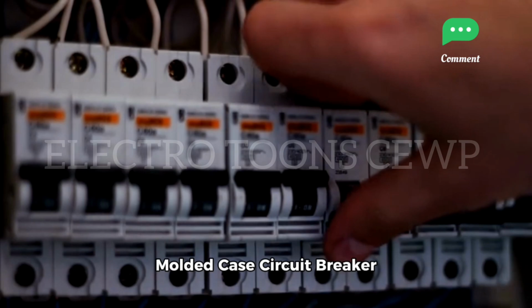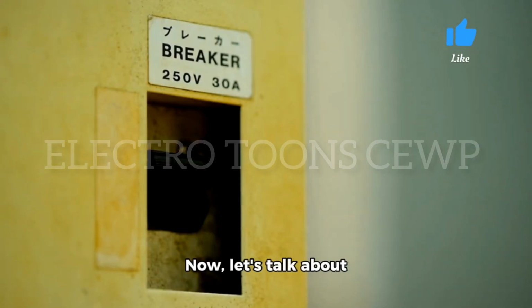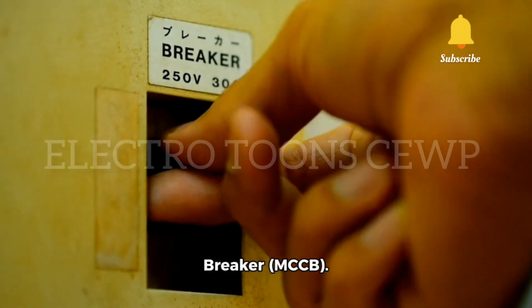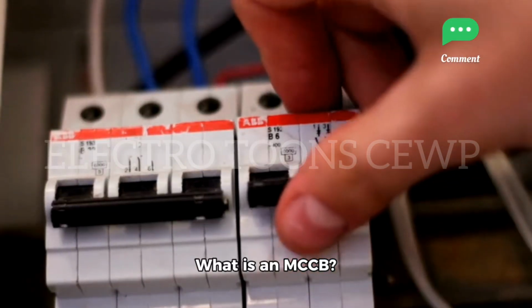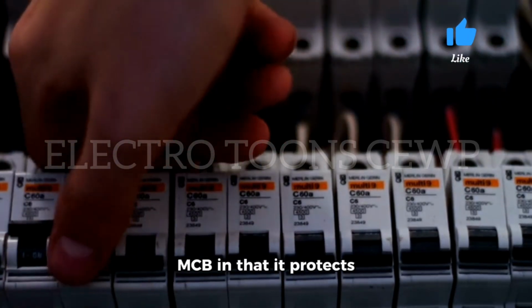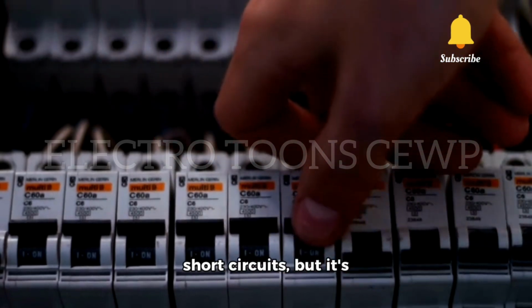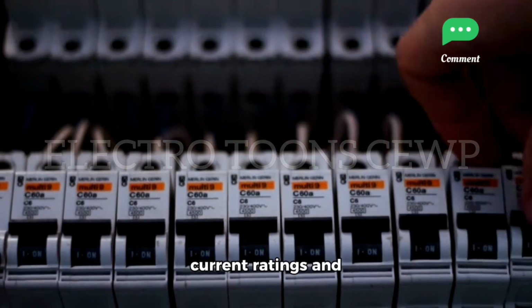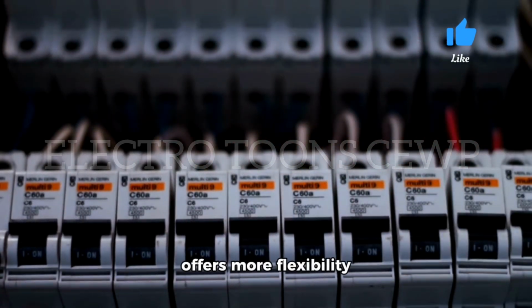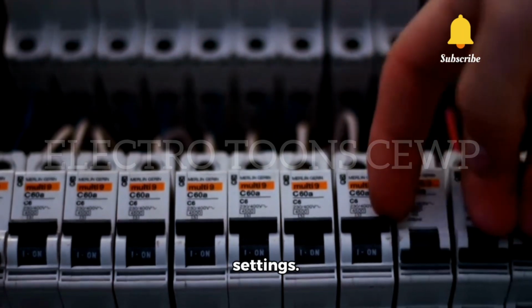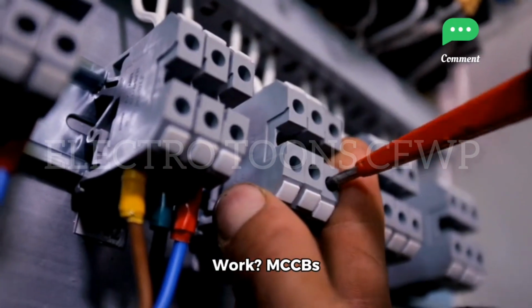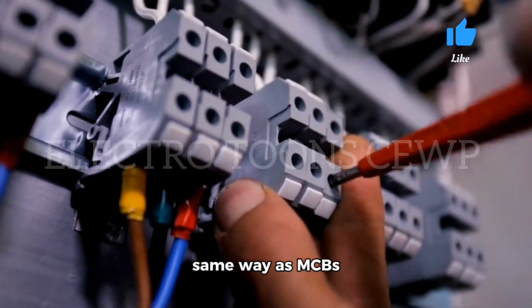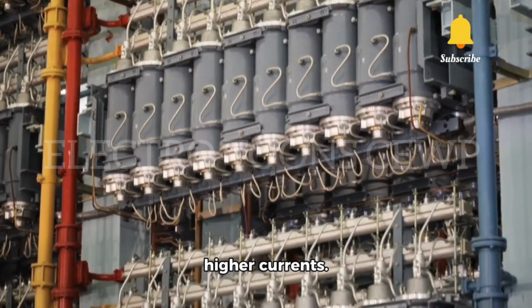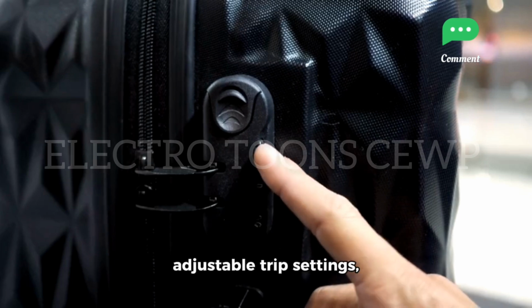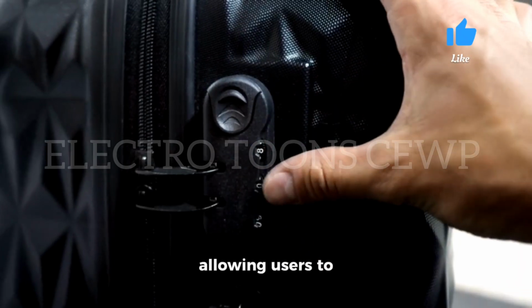MCCB, molded case circuit breaker. Now, let's talk about the molded case circuit breaker, MCCB. What is an MCCB? An MCCB is similar to an MCB in that it protects against overloads and short circuits, but it's designed for higher current ratings and offers more flexibility in terms of protection settings. How does an MCCB work? MCCBs operate in the same way as MCBs but can handle higher currents.